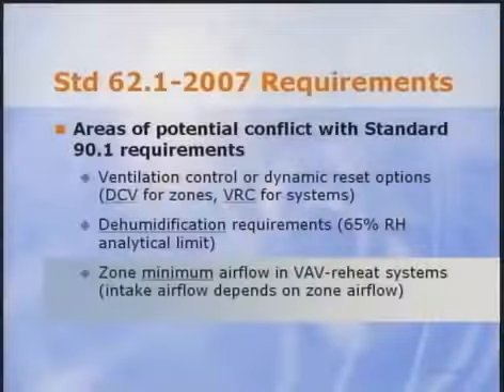It must be high enough to ensure proper ventilation at all load conditions. To comply with Standard 62, designers must use the multiple zone system equations, which relate zone outdoor airflow to intake flow at the central air handler. The two standards would conflict if the required Standard 90.1 settings were lower than the Standard 62 minimum outdoor airflow, but that doesn't happen. Of course, that doesn't mean that complying with the two standards is easy. Let's take a closer look.